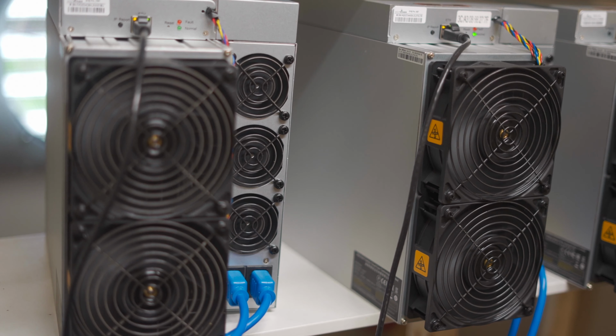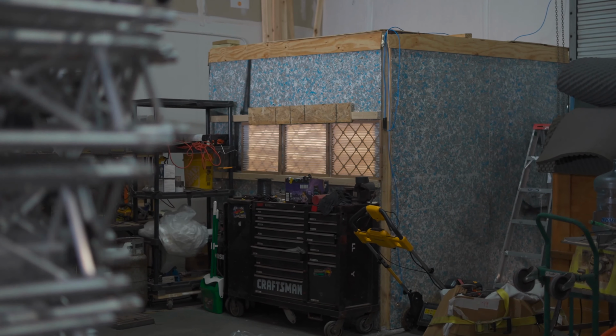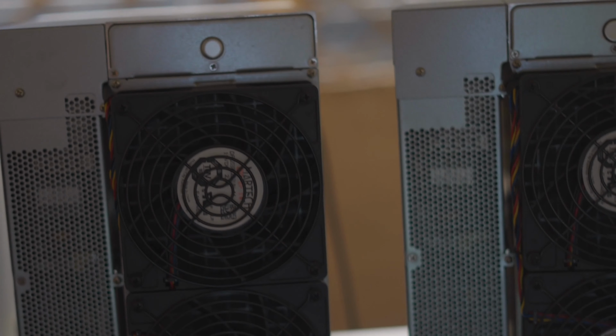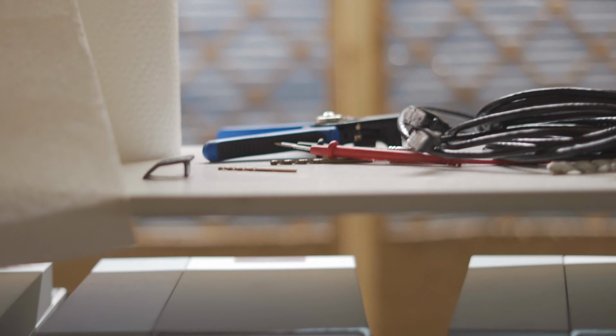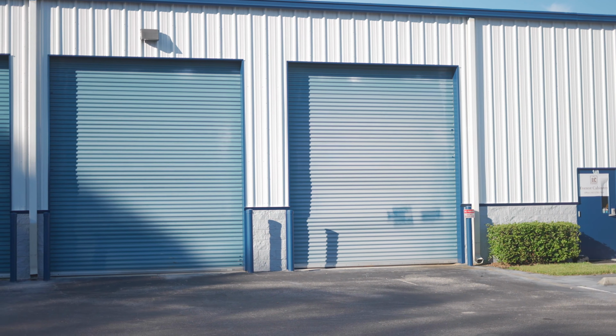At my setup, I have a big industrial fan built into an exterior door of my warehouse, in this small dedicated room. The fan is designed to replace the entire volume of air in there with cool, filtered air every 6 seconds or so. Then at the front of the warehouse, 2 very large doors are cracked just enough from the floor to allow that same amount of air to replace it.